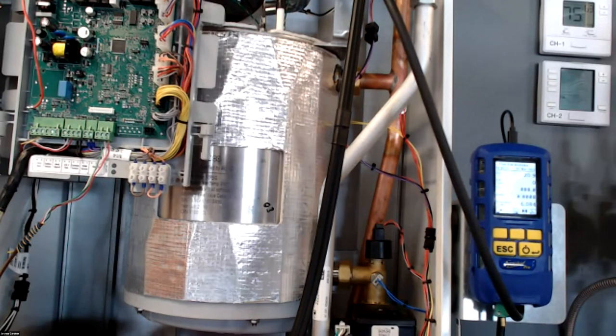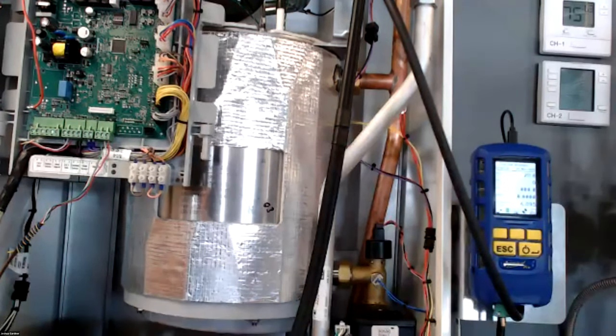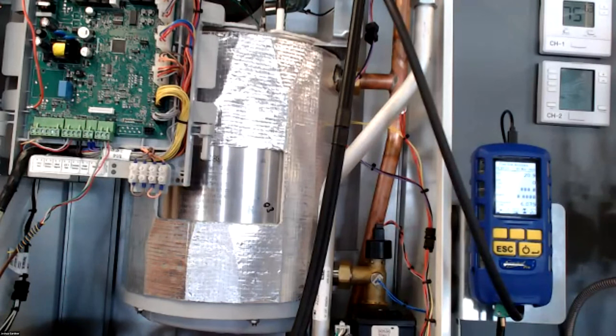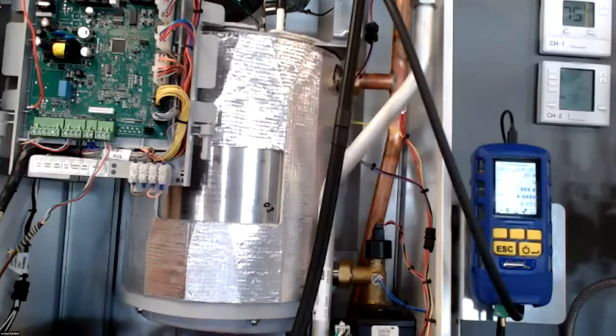Typically, I don't think I've ever had that issue where everything's in spec and the boiler is installed correctly, where we've had CO that's been drastically high out of parameter and our O2's been in check and our CO2's been in check. So does that mean it's possibly a result of cross-contamination?